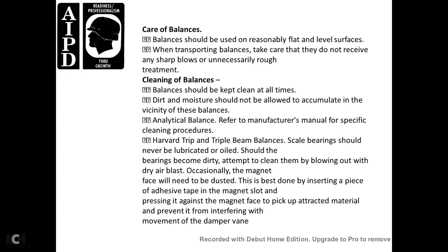Care of Balances: balances should be kept on reasonably firm and leveled surfaces. When transporting, take care that they do not receive any sharp blows or unnecessarily rough treatment. Balances should be kept clean and dry at all times; moisture should not be allowed to accumulate near the balance. For analytical balances, refer to the manufacturer's manual for specific cleaning procedures. For Harvard trip and triple beam balances, bearings should never be lubricated or oiled; if they become dirty, attempt to clean them by blowing out with an air blast. Occasionally a magnet face may need to be dusted by inserting adhesive tape into the magnet slot to pick up attracted material.